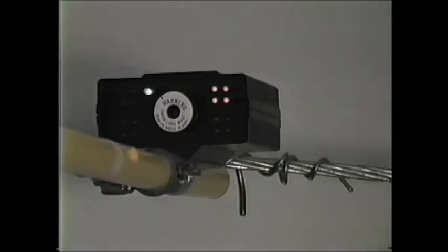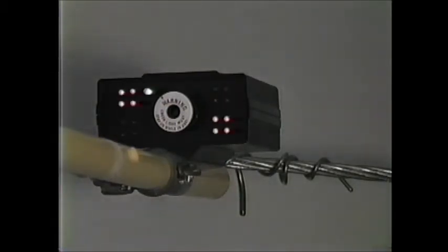This would be the normal operating voltage for a 12,470 volt system, 13.8, or a 14.4 KV system. This signal would indicate induced voltage if you were testing a 34.5 KV system or if you were working on a transmission line.